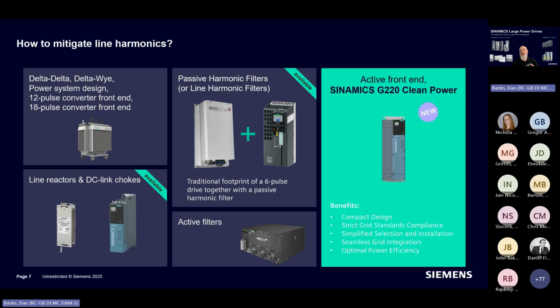I'd say in the UK, it's much more common to see active filters. This is an example of an active filter down there. What these devices do is they literally measure the harmonic noise and they generate the anti-phase signal. So they cancel it out and they give you that much lower effect. In fact, you could size those if you wanted to go all the way to 0.